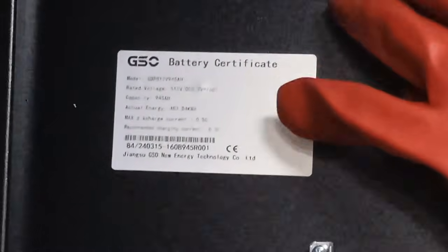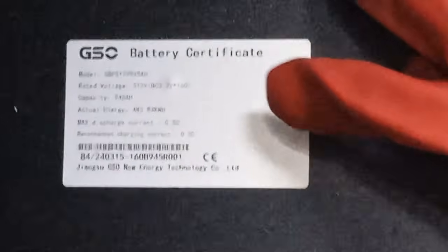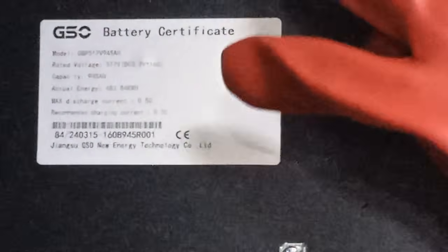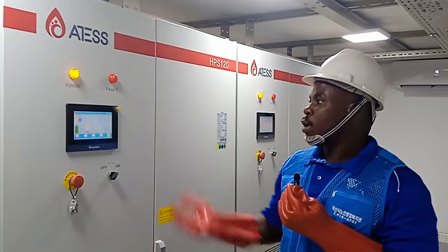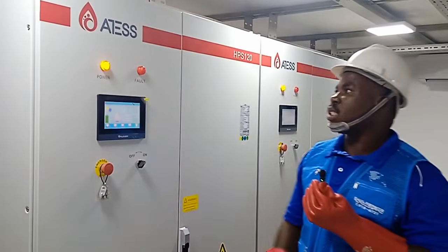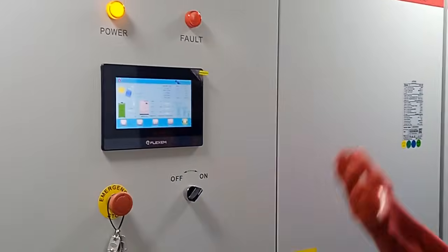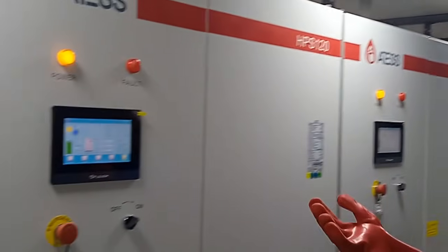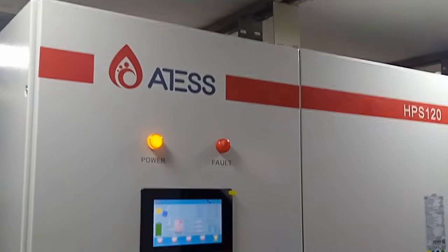As you can see, the actual energy is 483.84 kilowatt hour. The capacity is 945 amp hour. Then the rated voltage is 512 volts. It has a maximum discharge current of 0.5 C and a recommended charging current of 0.2 C. Now we head over to the inverter. In this power station we have 2 units of ATESS power HPS 120. This is the first inverter and this is the second inverter. This is a hybrid inverter with a continuous output power of 120 kilowatts.